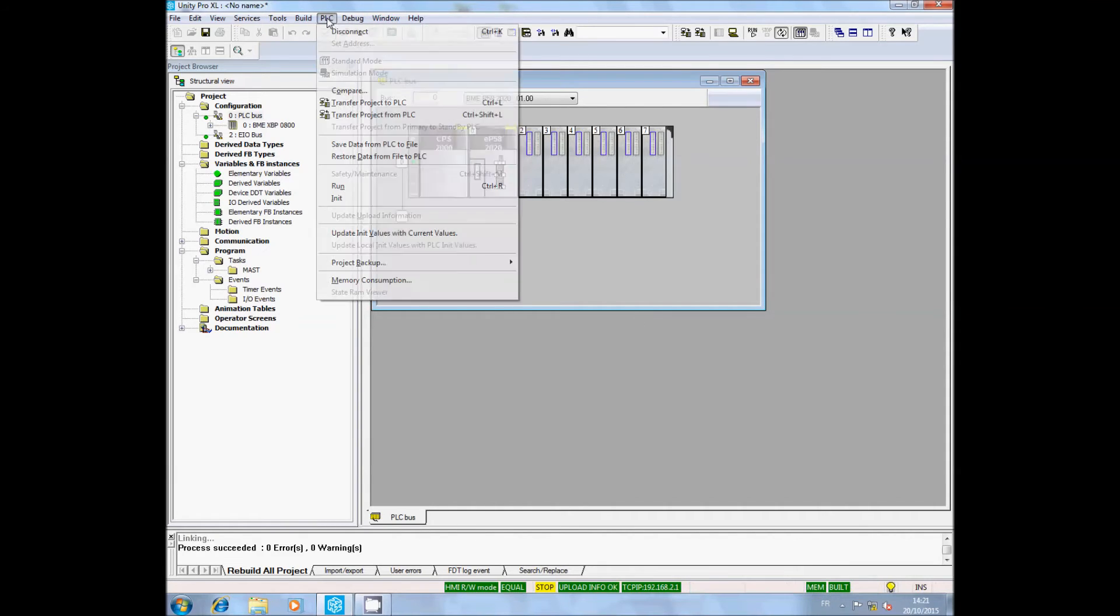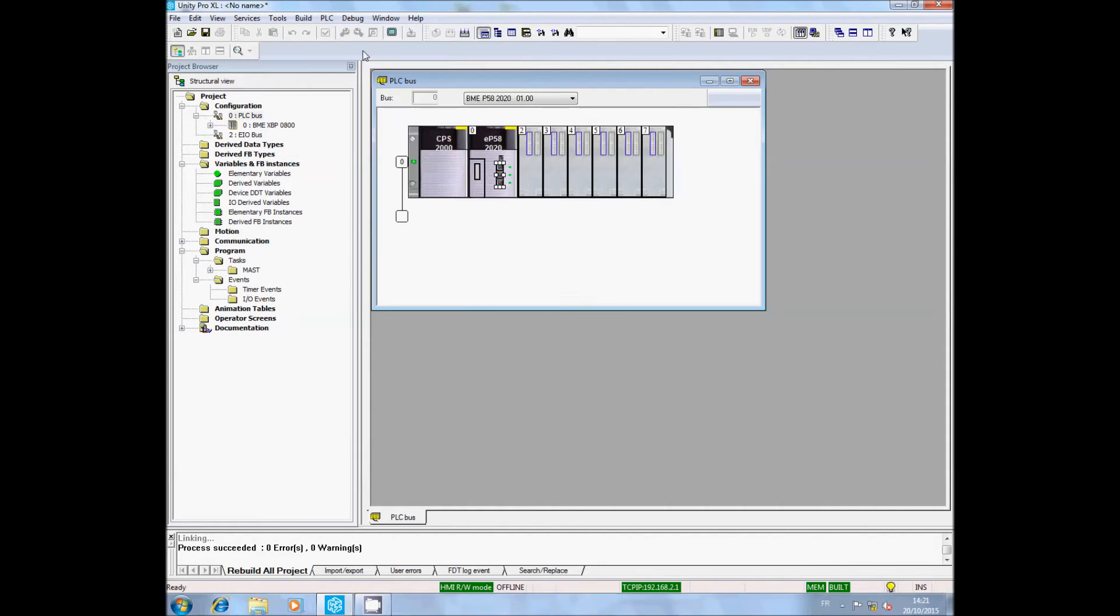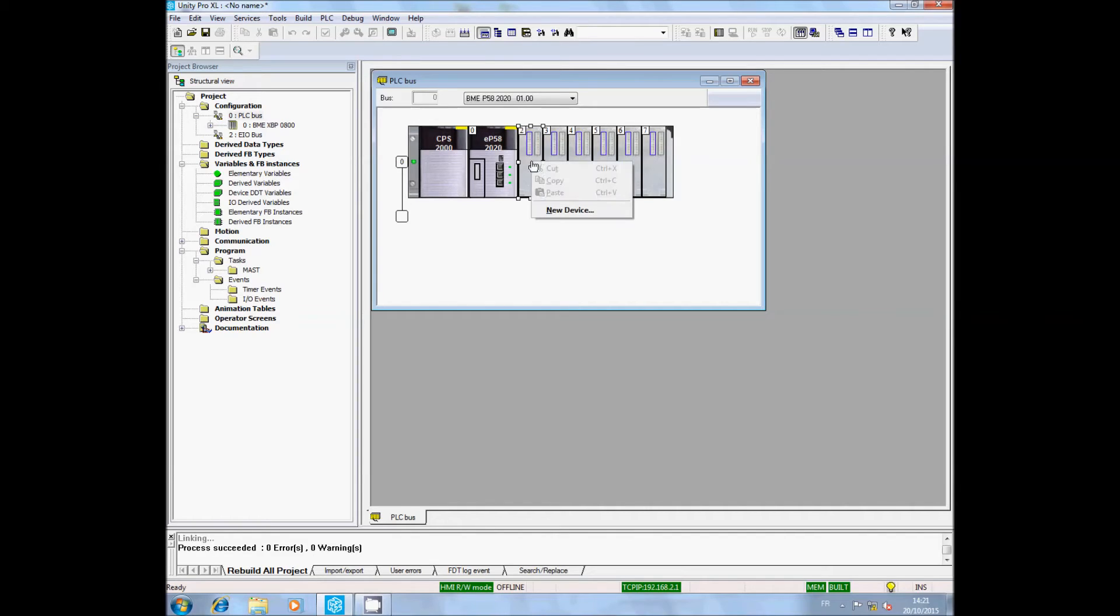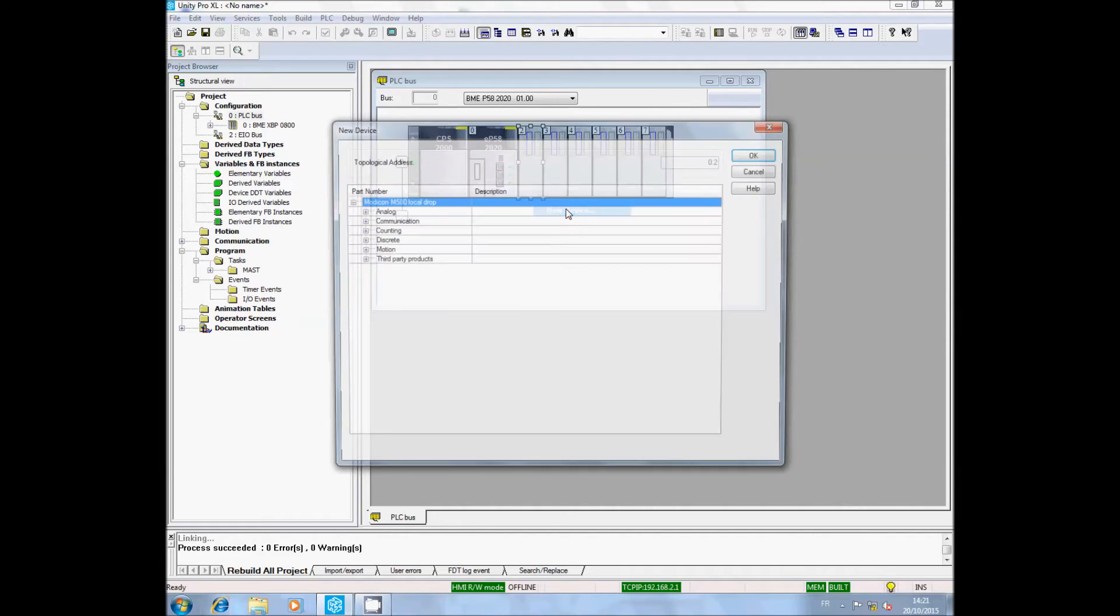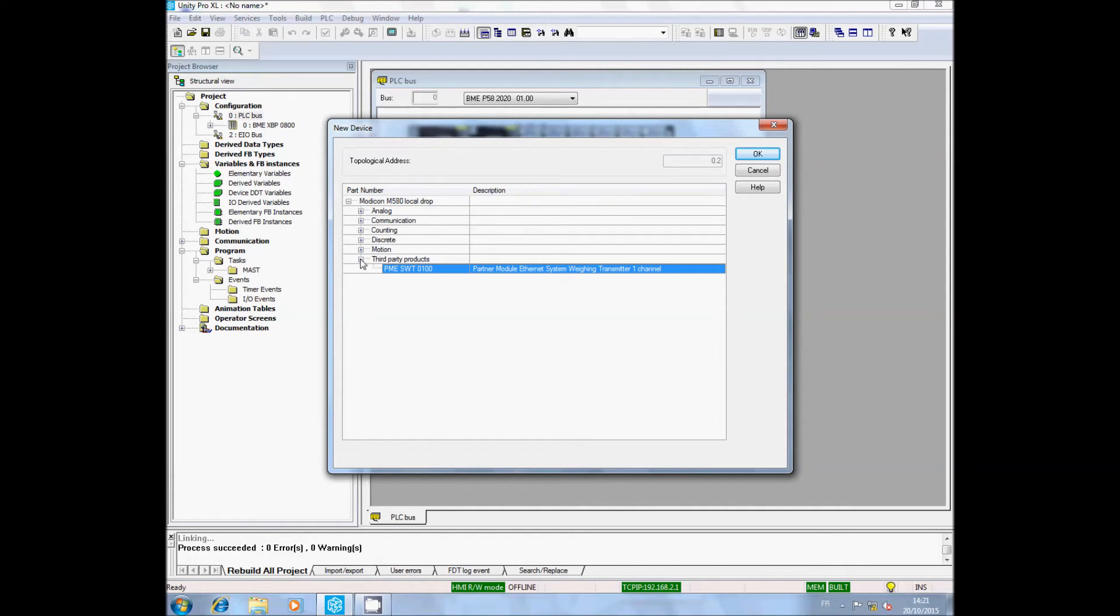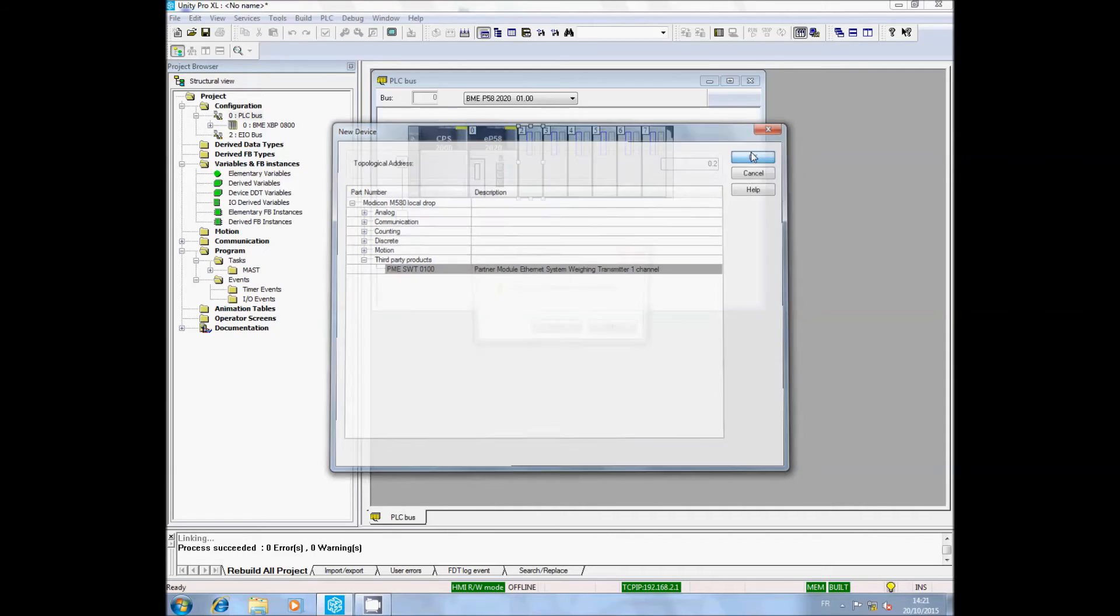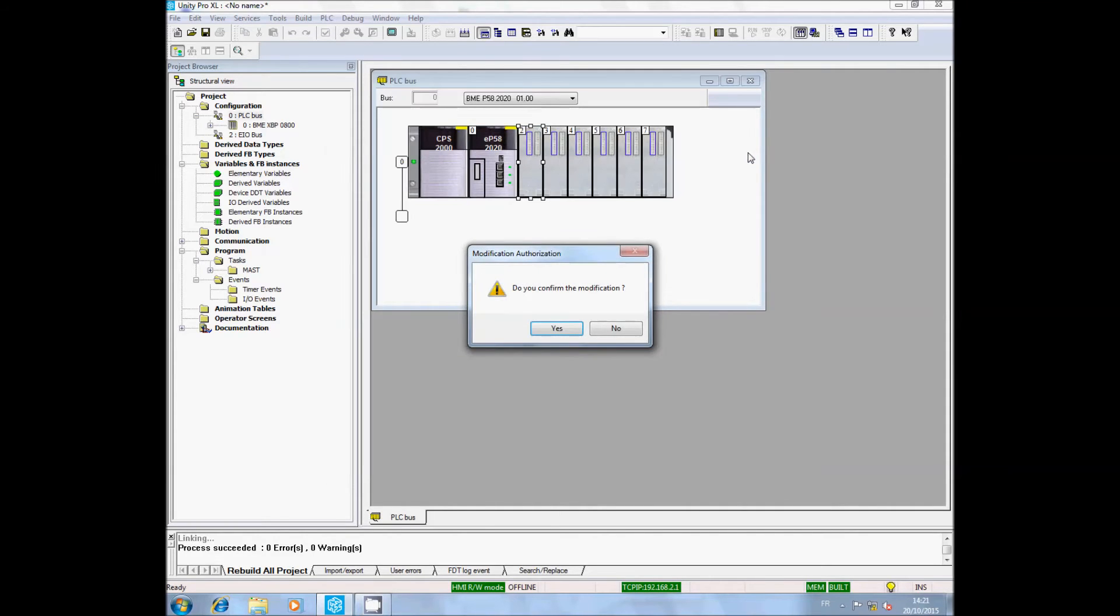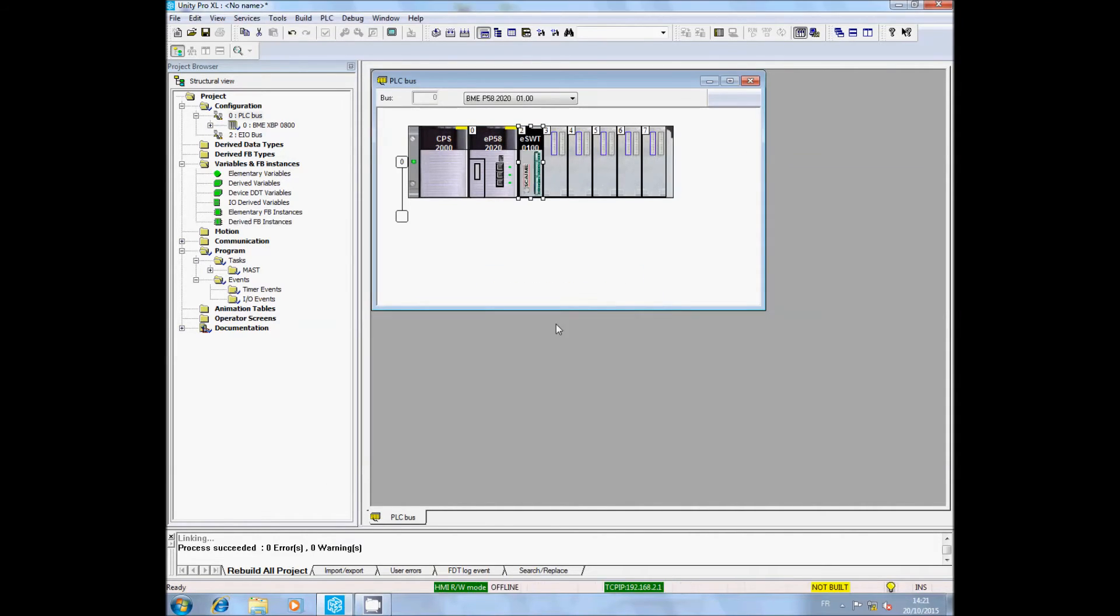In the PLC bus window, right-click on the slot where you have installed the BME SWT and click on New Device. A new window appears with a list of devices. In third-party products, choose the BME SWT. Click Yes when Unity asks you to confirm the modification. The BME SWT is added to the rack.